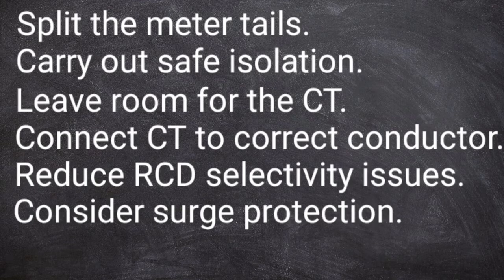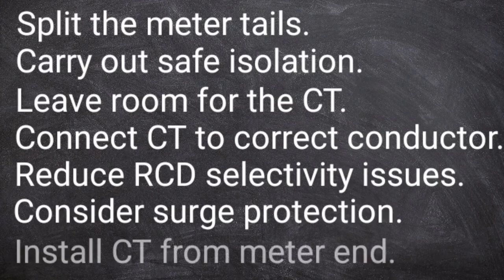And then finally, we saw the importance of making sure that we installed the CT from the mains connection. We want to make sure that if we're going to be installing that CT, that we start at the meter end so that we don't have to push that relatively large CT through any holes in walls and things like that. If you find yourself in a situation where you need to extend the cable, Gary, what's the recommendation? What type of cable would be suggested to use to extend the CT cable? You're going to be using Cat5 cable, and they recommend you use a screwed connection to join those conductors together. Remembering you're only going to need to use one pair, so in other words, two conductors within a Cat5 cable to extend the CT meter cable in order to make sure it can reach the actual EV charging point itself.